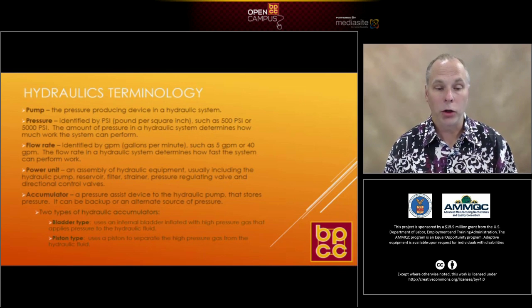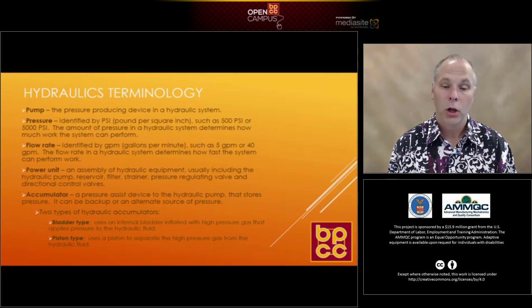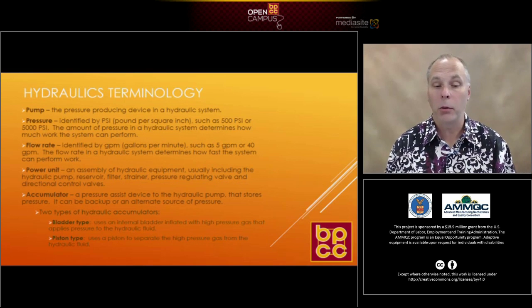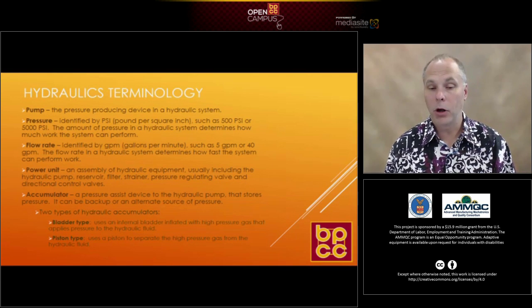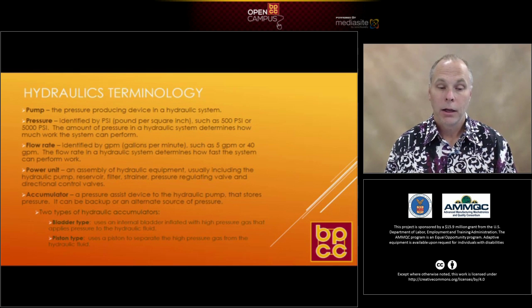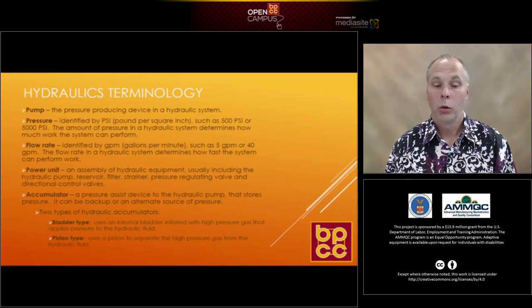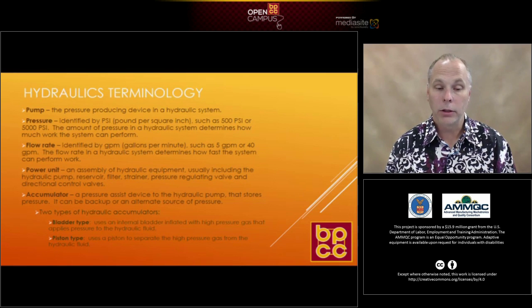Away from the power unit you may have what they call an accumulator. The accumulator is a pressure assist device in a hydraulic system — it assists the hydraulic pump, stores pressure usually at a remote location, and can act as a backup or alternative source for pressure. There are two types: the bladder type, which uses an internal bladder inflated with high-pressure gas to apply pressure to the hydraulic fluid, and the piston type, which uses a piston to separate high-pressure gas from the hydraulic fluid.